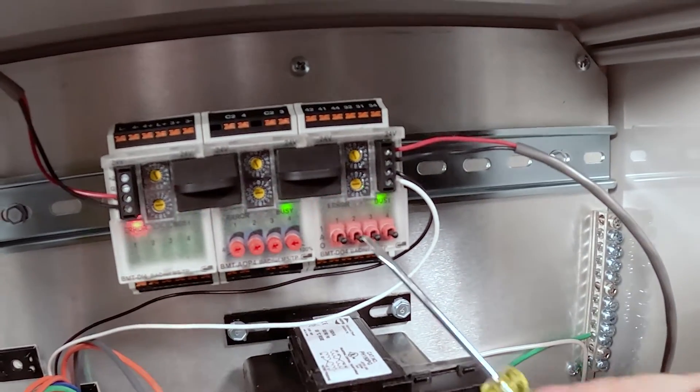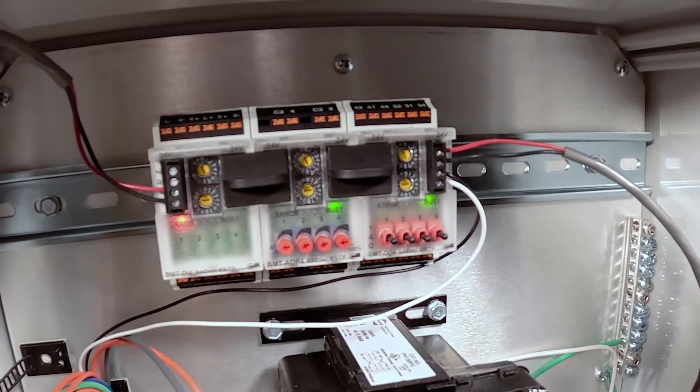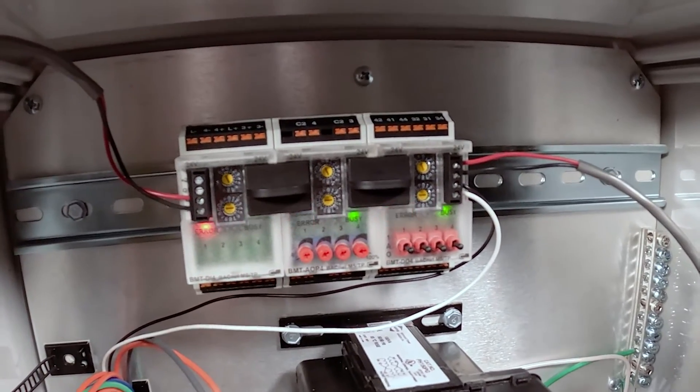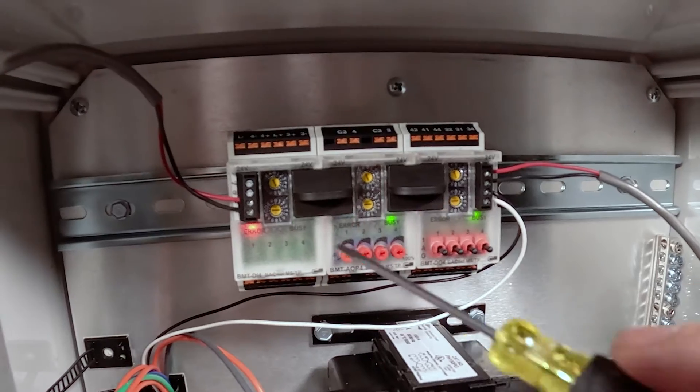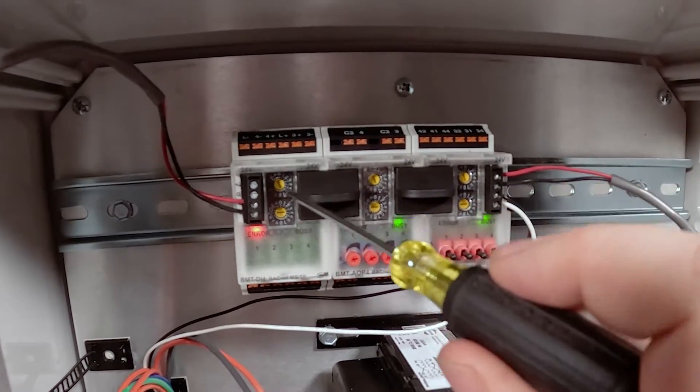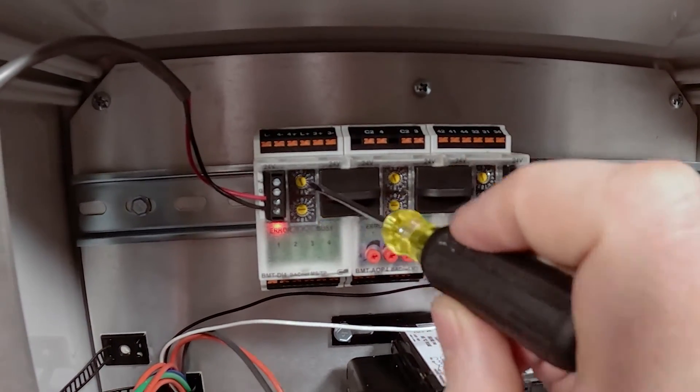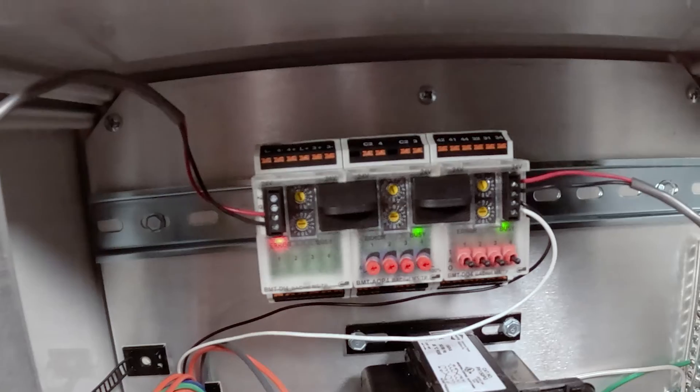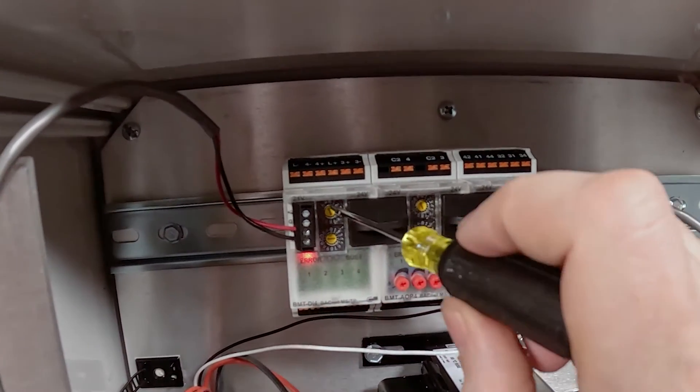Now that all of our modules are in baud rate mode, we can set them to their address. First thing we're going to do is set the first one to two because your controller is always going to be one.